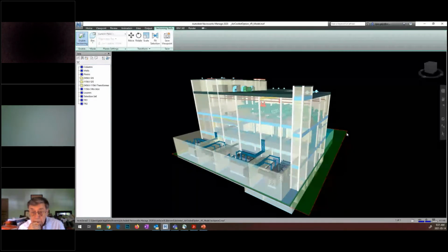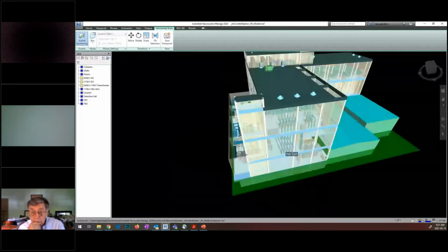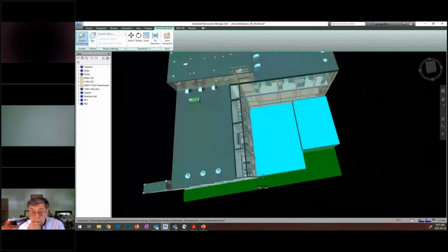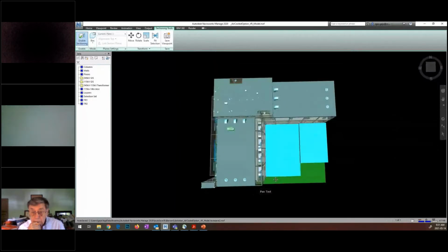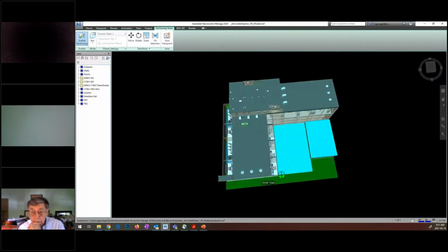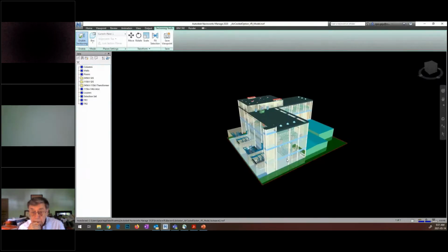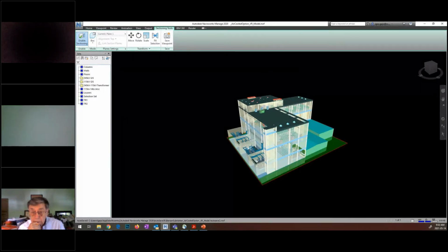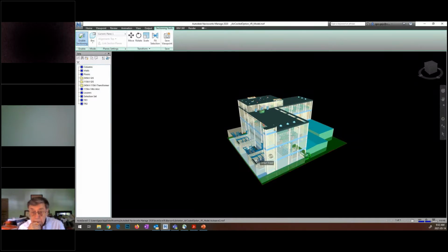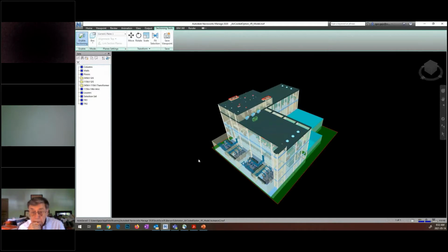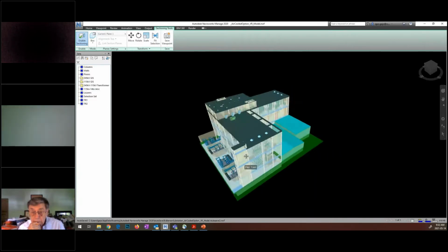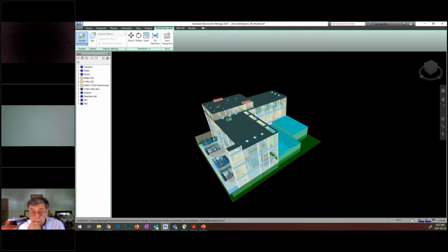We had a lot of constraints here. That's why we ended up with this odd-shaped L-shaped building, where we had to fit three voltage levels: 345 kV SF6 GIS equipment, 115 kV SF6 GIS equipment, and 14.4 kV medium voltage equipment. There were also supposed to be high voltage transformers, phase shifters, shunt reactors, and so on. Just from this, you can imagine how big the substation is.